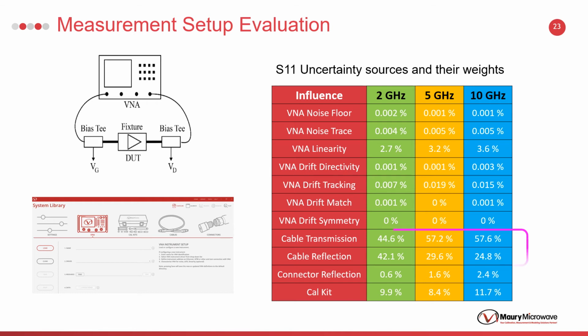the cables and calibration kit have large contributions to the total uncertainty. This is why we recommend phase-stable cables and regular calibrations of your cal kits. It might be time to invest in some phase-stable coaxial cables and to calibrate your cal kits.